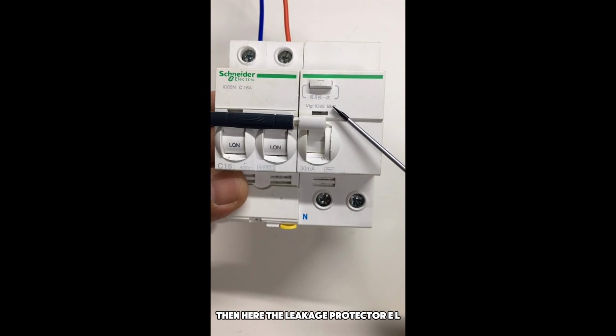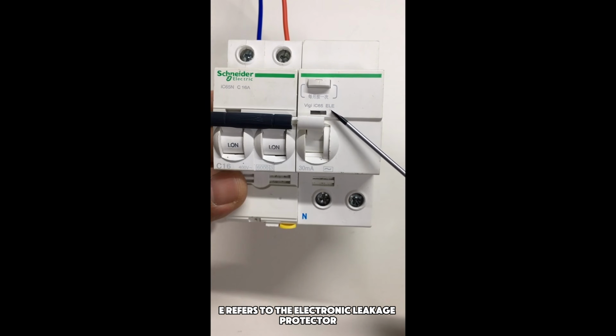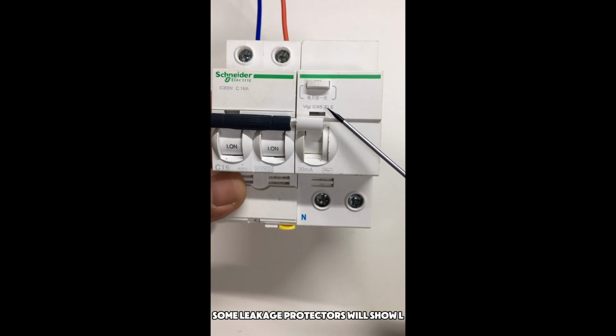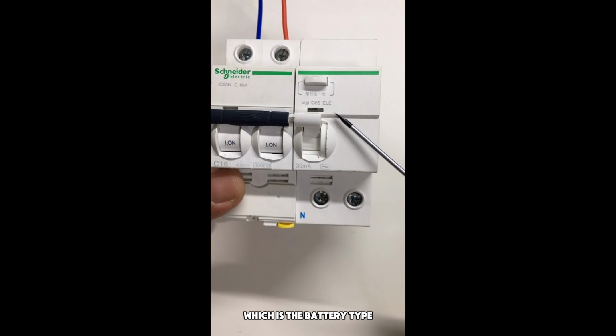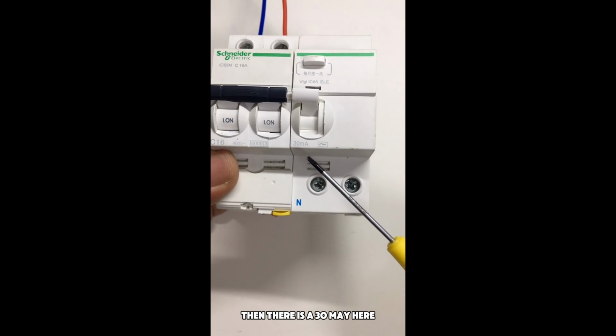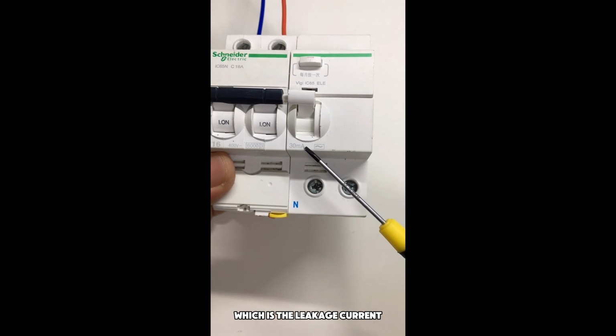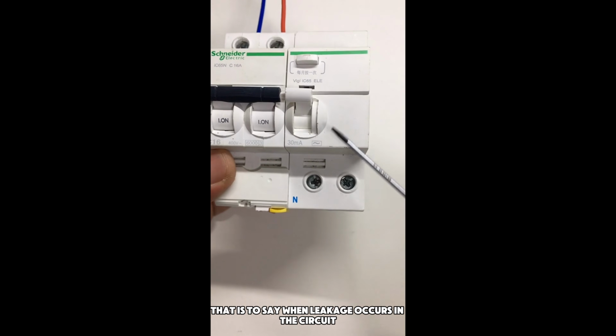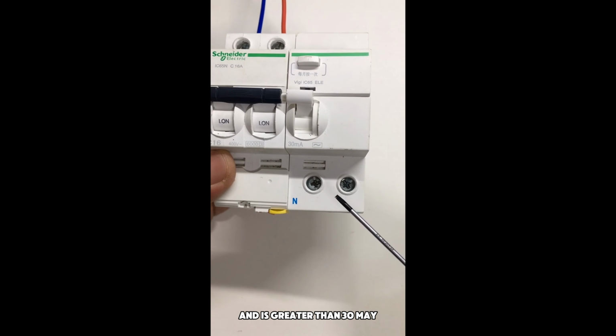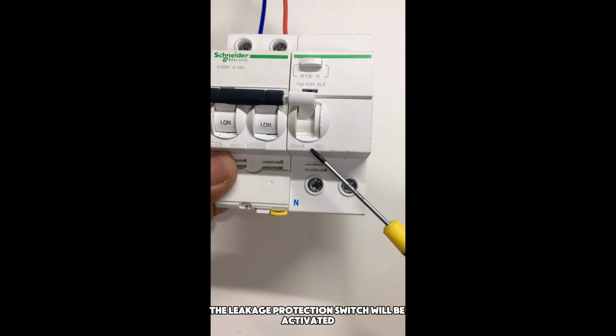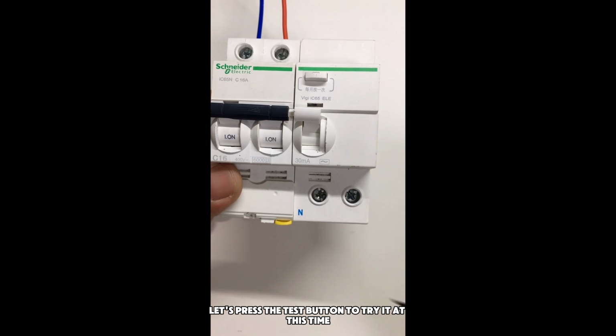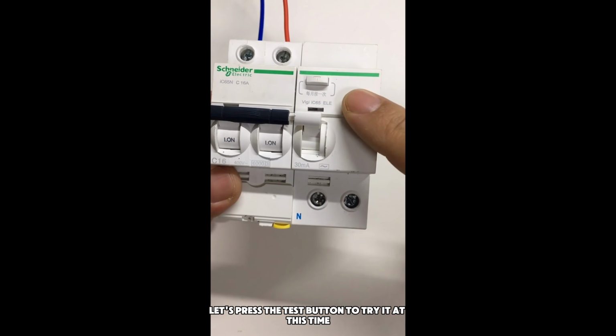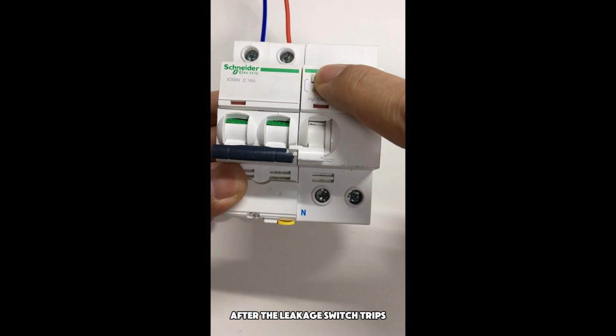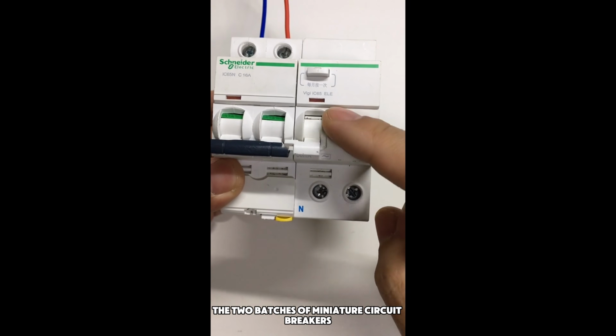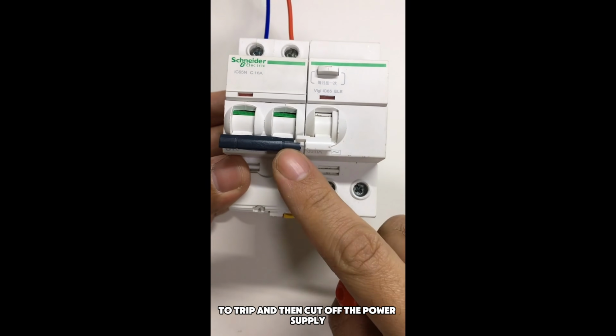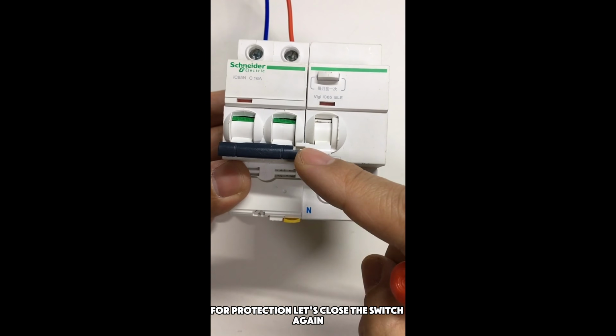Then here, the leakage protector ELE refers to the electronic leakage protector. Some leakage protectors will show ELM, which is the electromagnetic type. Then there is a 30 mA here, which is the leakage current. That is to say, when leakage occurs in the circuit and is greater than 30 mA, the leakage protection switch will be activated. Let's press the test button to try it. At this time, after the leakage switch trips, it can cause the 2-pole miniature circuit breaker to trip and then cut off the power supply for protection.